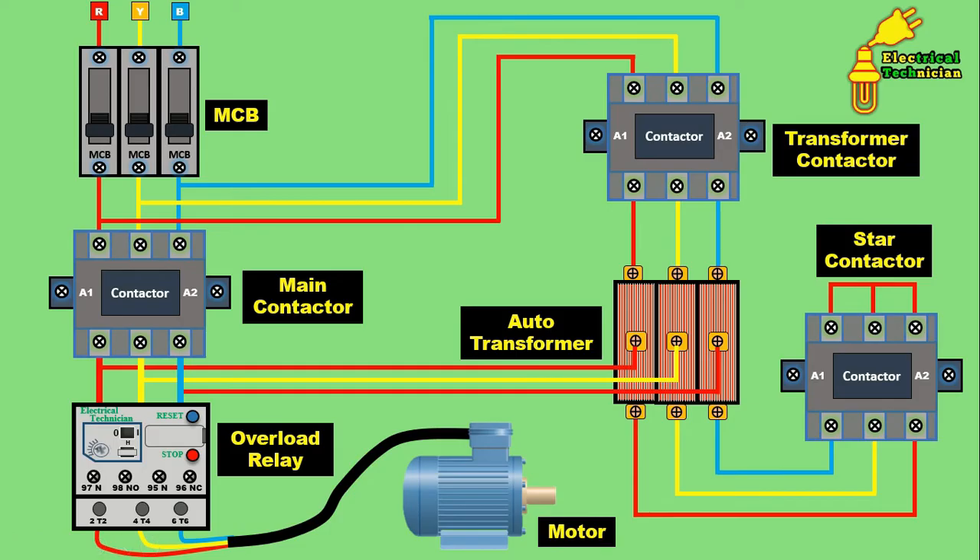Now let's understand how this auto transformer starter works. The induction motor takes a high amount of current during starting — almost five to six times the full load current. The motor winding cannot tolerate this much current; if five to six times starting current is applied, the motor winding will slowly burn out and the motor can be destroyed. For protection, at starting time we apply less voltage. In the transformer, tapping is connected — suppose the tapping is at 70%, then 70% of the applied voltage will be obtained at the tapping output, and through a wire the motor is connected to this.